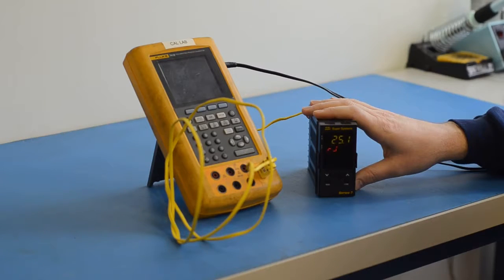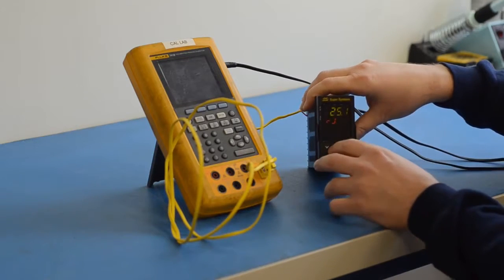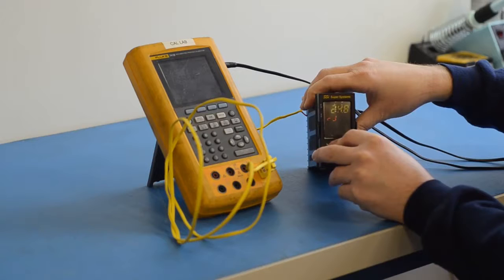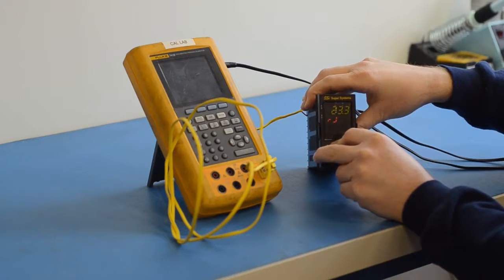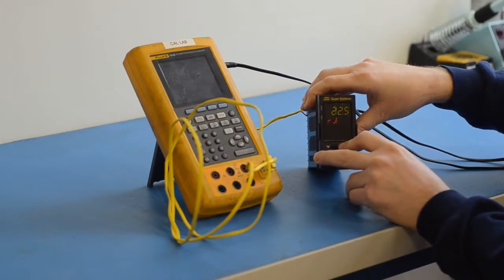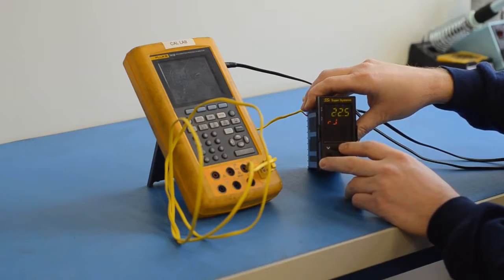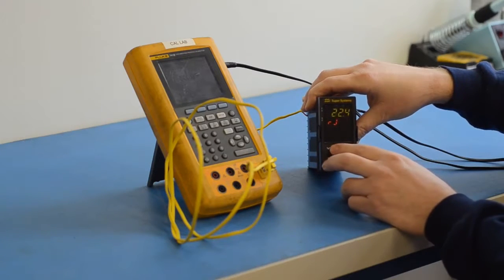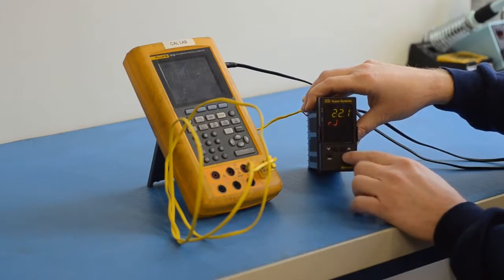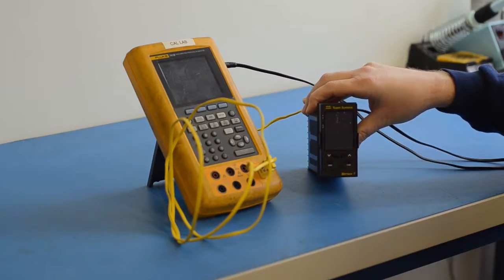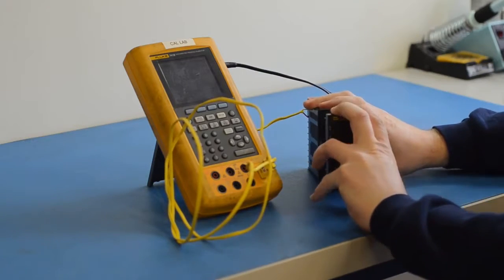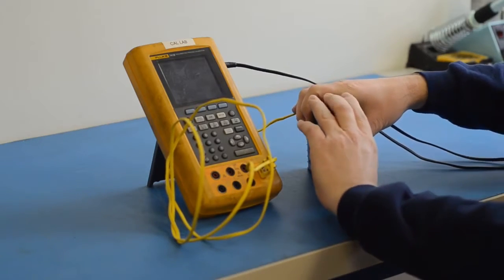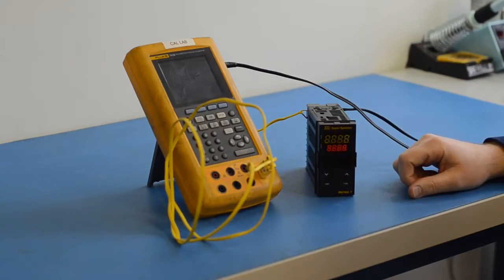So we know that we are approximately 1 degree high in Fahrenheit. We want to make an adjustment then down on this value, so I'm taking it down from 25 to 22. Pressing the function button, it will then adjust our cold junction. And now, in order to check it again, we will need to remove it, relatch our jumper, reinsert it into the case, and see what the result is.